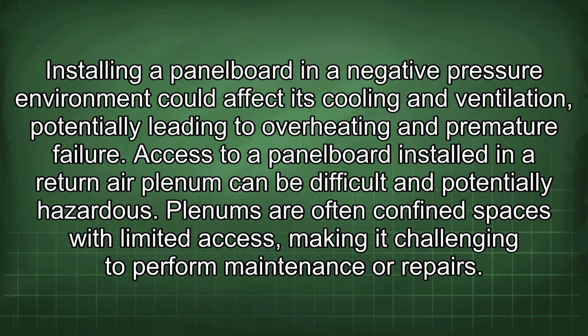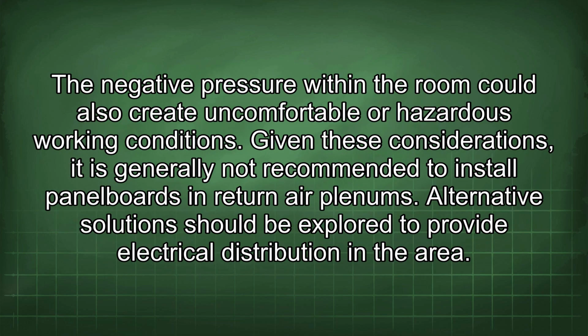Access to a panelboard installed in a return air plenum can be difficult and potentially hazardous. Plenums are often confined spaces with limited access, making it challenging to perform maintenance or repairs. The negative pressure within the room could also create uncomfortable or hazardous working conditions. Given these considerations, it is generally not recommended to install panelboards in return air plenums. Alternative solutions should be explored to provide electrical distribution in the area.